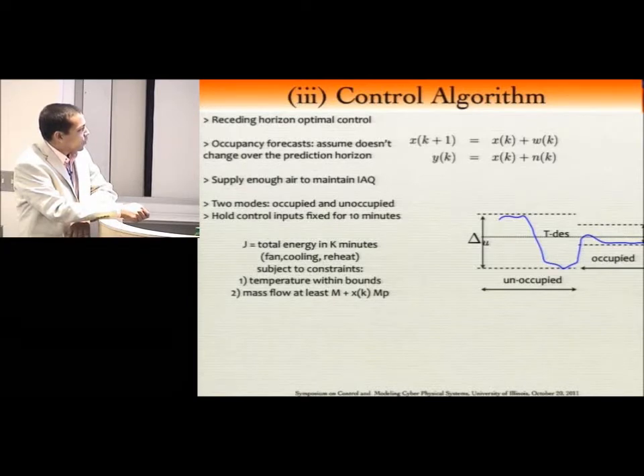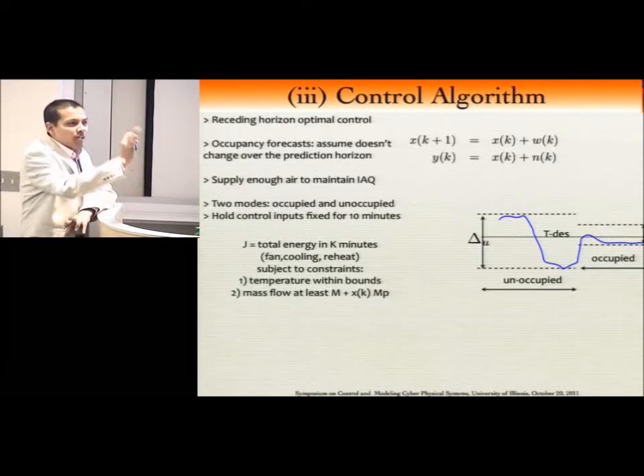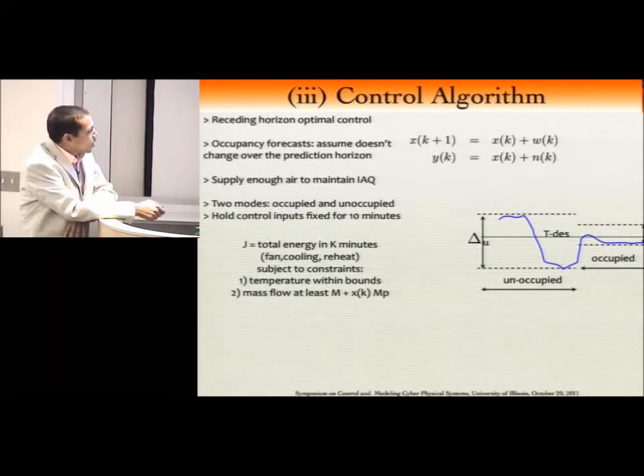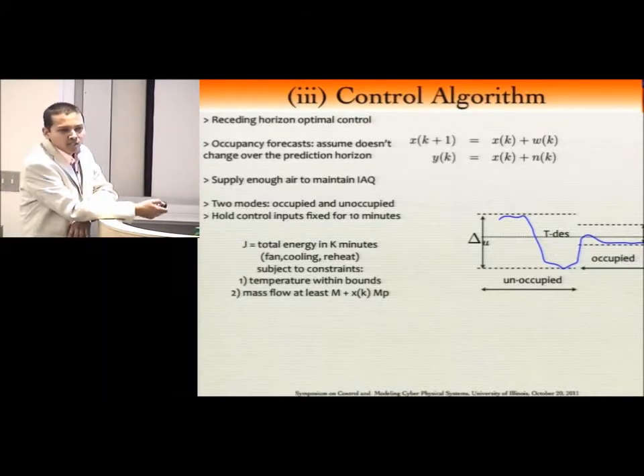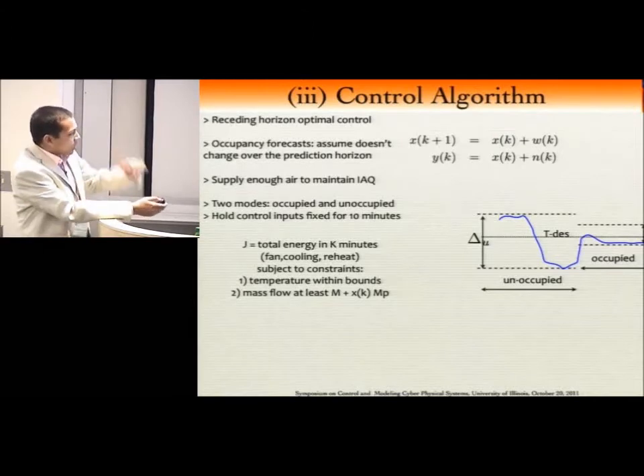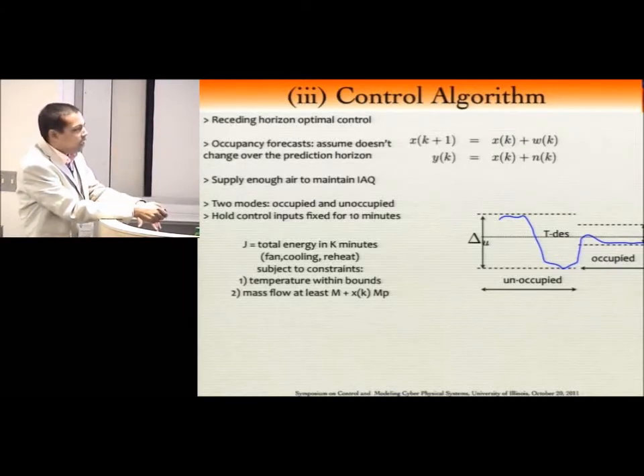If you are currently in the unoccupied mode, you assume that you are going to be in the unoccupied mode for the next half an hour, and you are allowed to vary the temperature within a wider range. The indoor air and the supply air can go down to a particular level, but not below that. Whereas if I'm in the occupied mode, then I'm allowed to vary temperature only in a smaller range. All right?